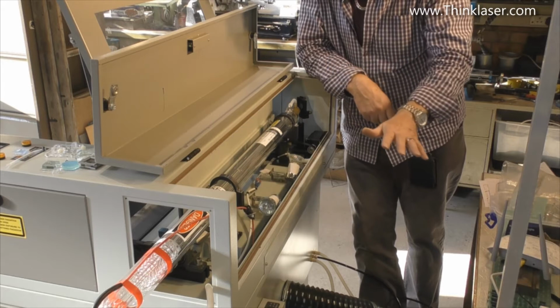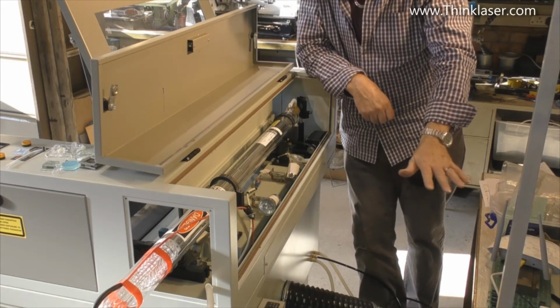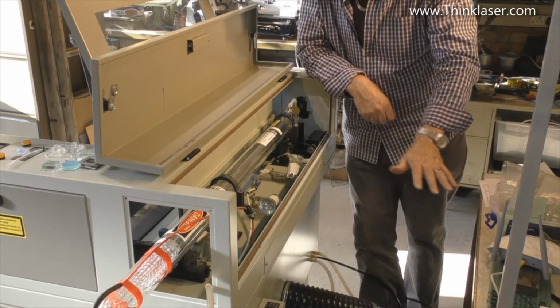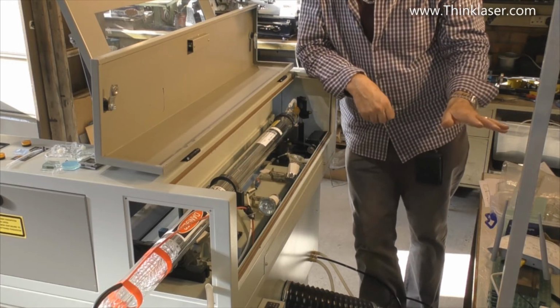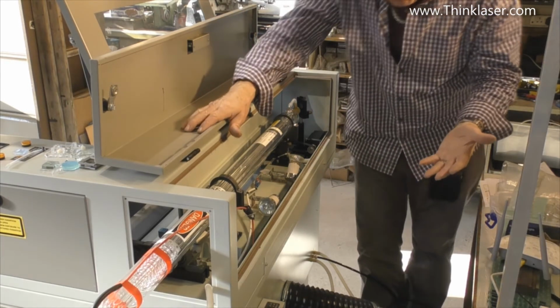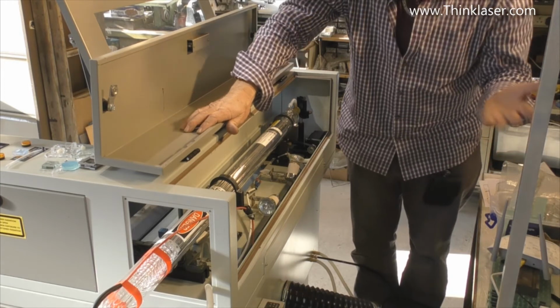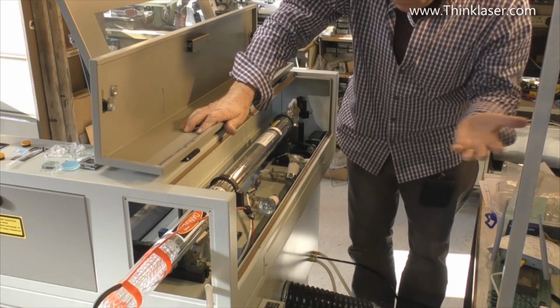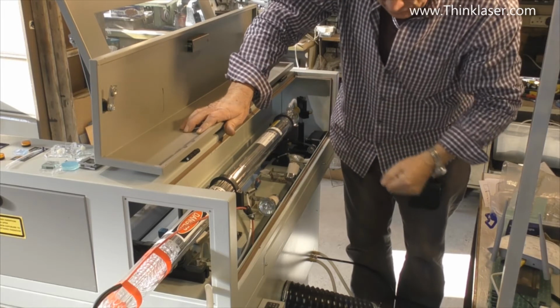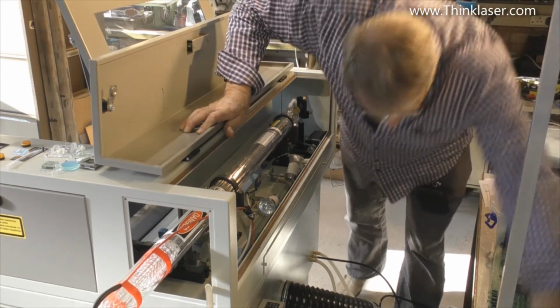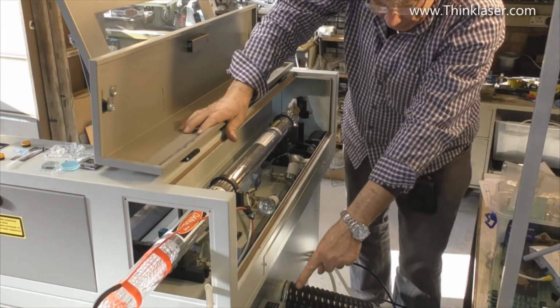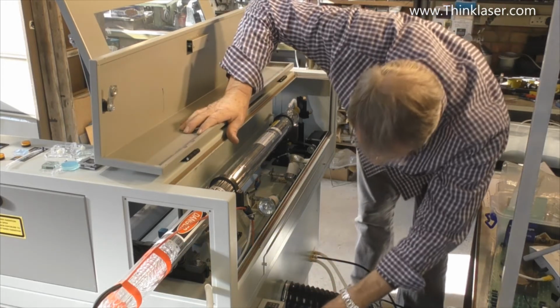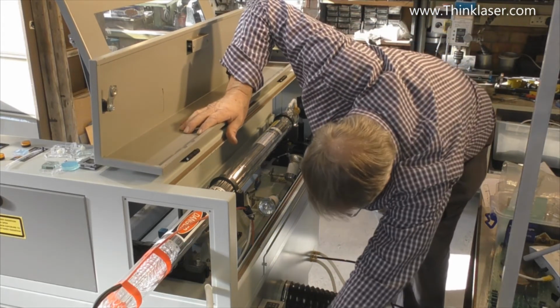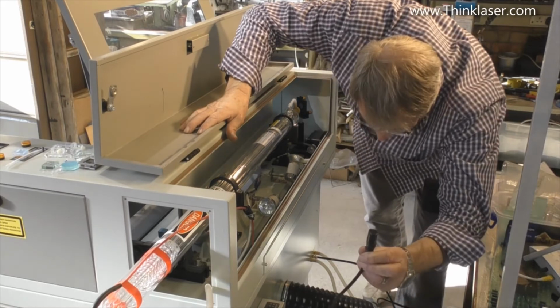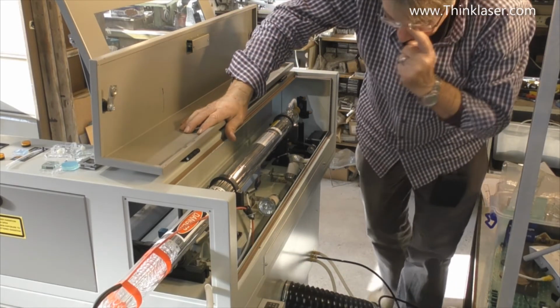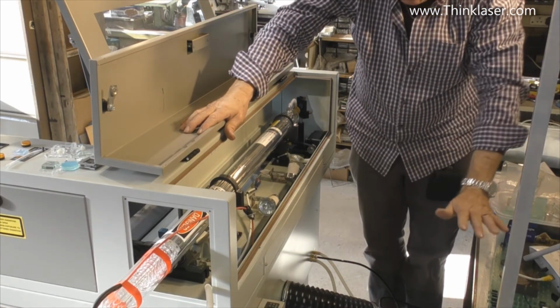Now, do not disconnect your machine from the power supply while you're doing that, because it probably needs to leak away to earth somewhere. If you disconnect it from earth, it might not leak away. So only when you get to the point where you're going to mess around with this should we disconnect the machine. Now down at the bottom there, it's clearly marked with a 220 volt input. Disconnect that plug. And now you know the machine is completely safe.